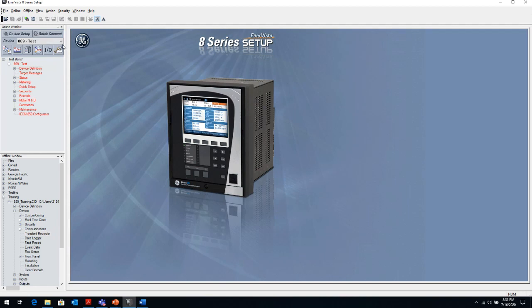Just clicking on this icon, the relay will download the service report. And that service report contains every element in the relay. It contains a setting file, the oscillography, a sequence of events, any data that's logged in the relay, any diagnostic information that the relay is gathering, RTD readings, metering information, and a whole host of stuff.